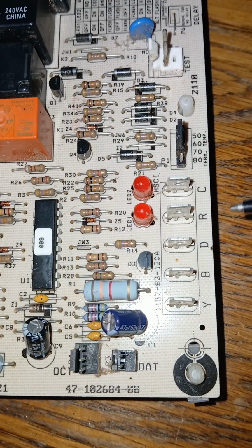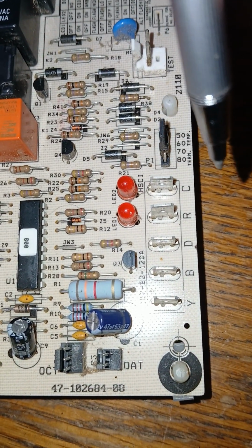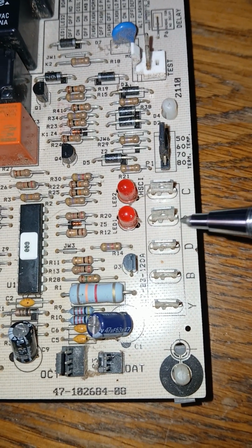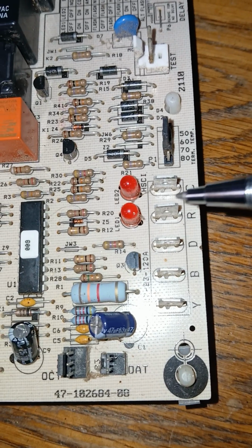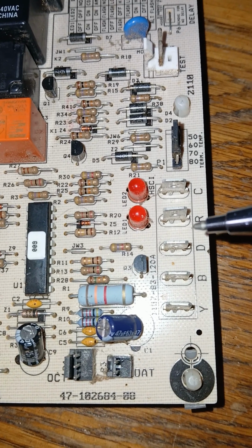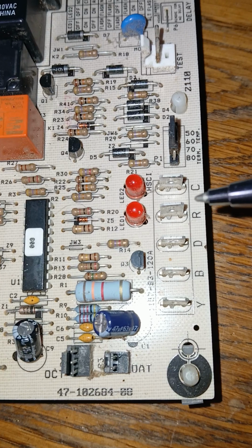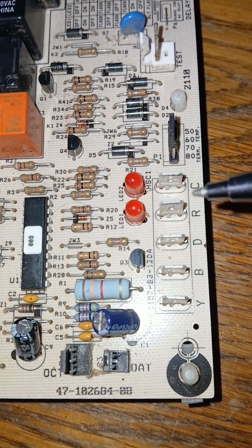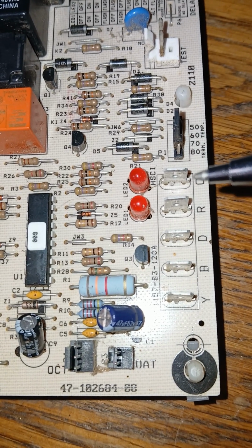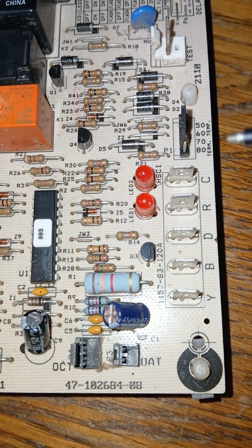And so the red wire comes in at 24 volts. Now, one caveat here: if you read this on your meter and it reads 26 to 27 volts, that's perfectly fine. There's a variance that's allowable. So don't get up in arms thinking, oh, wow, I'm not exactly on 24 volts. If it reads 26, 27, plus or minus 28, perhaps you may be fine.